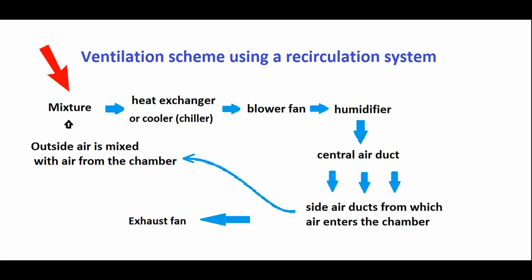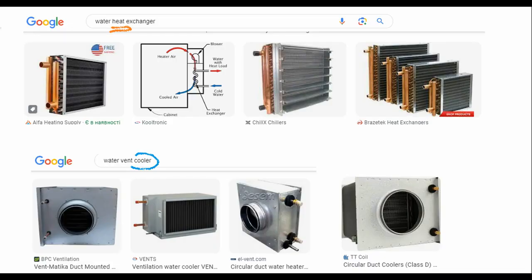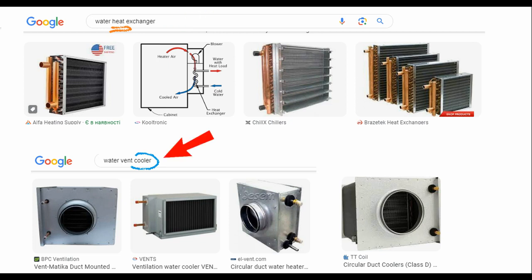So we mix the air. It then passes through a heat exchanger where it is heated, or through a cooler that is powered by a compressor or chiller where the air is cooled. The heat exchanger and cooler externally look almost the same. The difference is that hot water flows through the pipes of the heat exchanger, and freon or cold water enters the cooler.